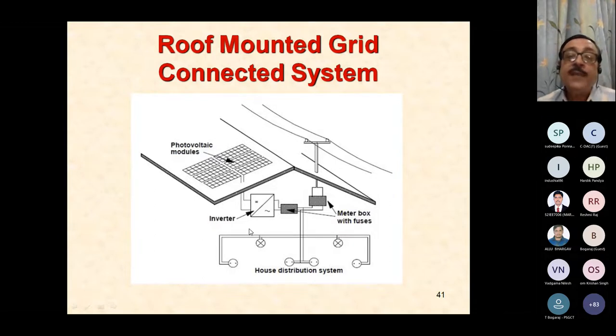So what do you do? You now need to solve the problem by putting in a battery backup and storing all the solar energy in your battery. There's no way out because you can't feed it back to the mains. So you store the energy in a battery. You have a big battery backup system, and in the evening when everybody comes back, that's the time you have to use that energy. You should not use the energy from the commercial supply. If you use the energy from the commercial supply after coming back in the evening, then you are not using the solar energy and you are not going to get any saving.